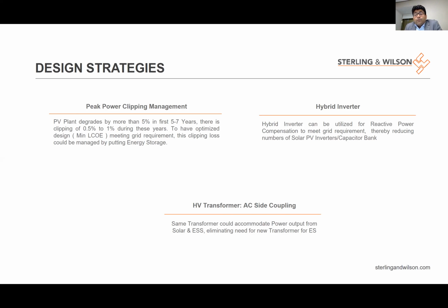If you're going for a plant with storage capacity, imagine a 100 megawatt solar power plant with 10 or 20 megawatt of storage, for which you'll put 5 or 10 megawatt of hybrid inverters. The same inverters could be utilized to meet reactive power compensation for the grid. So rather than designing your solar plant for a higher capacity of inverters to meet the reactive power of the grid, you can utilize the hybrid inverters and reduce your cost on the solar side, which overall brings down your levelized cost of electricity. This is the second strategy.